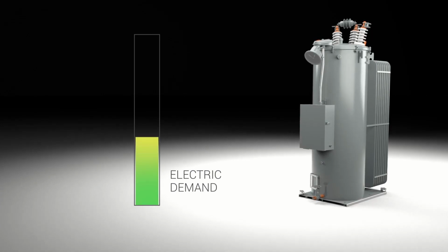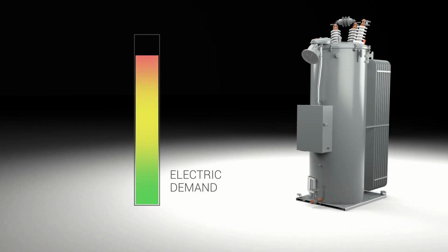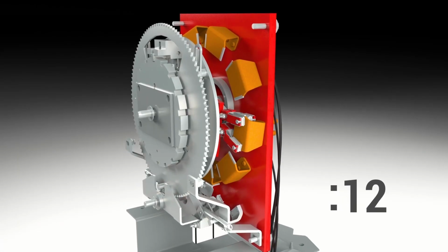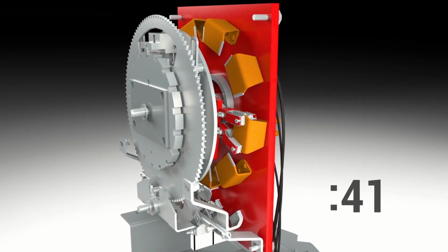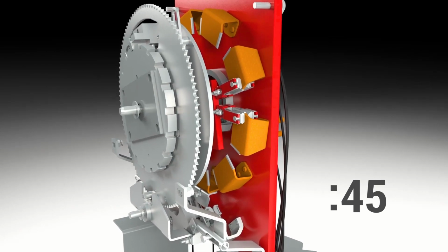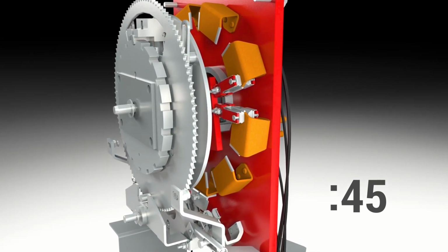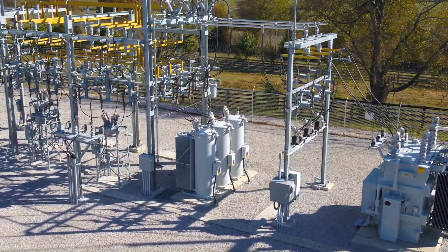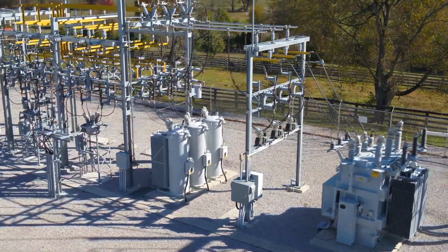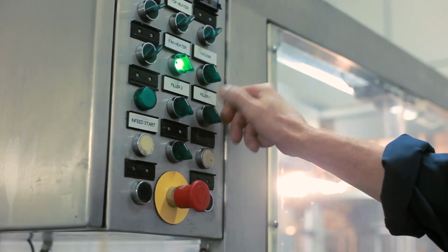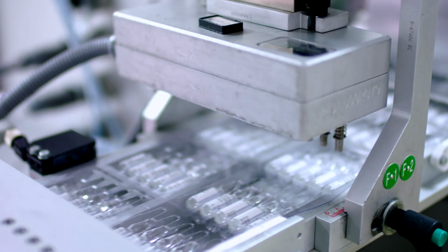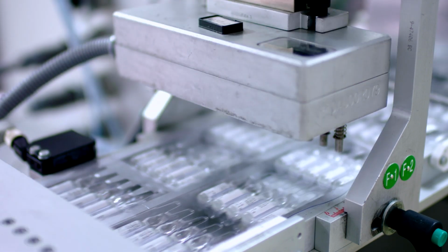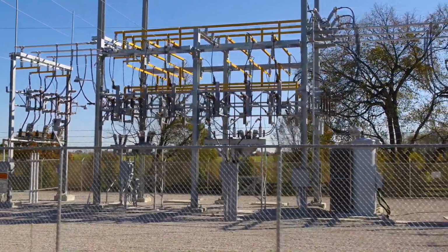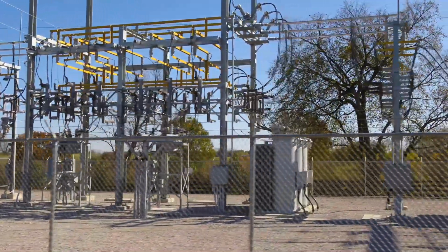Note that the regulator does not change tap positions instantaneously with a change in load. There will typically be a 45-second delay from the time load increases or decreases on a line before the regulator alters the voltage. The type of load near the substation being served dictates how often the regulator steps up and down. A regulator going to an industry that has a steady electric demand will remain fairly constant without changing positions. But a regulator serving a residential neighborhood typically will step up and down as load hits a peak when people get up to go to work, and later towards evening when they come home to eat dinner and spend their evenings in their houses.